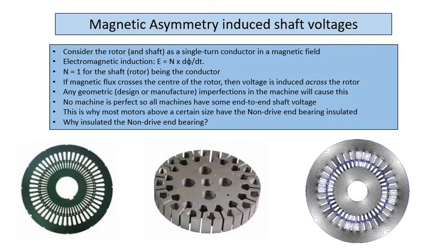so magnetic asymmetry causes end-to-end shaft voltages. Unbalanced power supply would cause both, because you'd have your effective stator frame voltage changing, and you'd have an end-to-end voltage. Magnetized machine components mainly cause circulating currents. I'll explain that just now, and end-to-end voltages. Electrostatically induced shaft voltages are effectively common mode because they normally originate from the driven load or prime mover. So your driven load and your voltage couples back and drives through the motor.